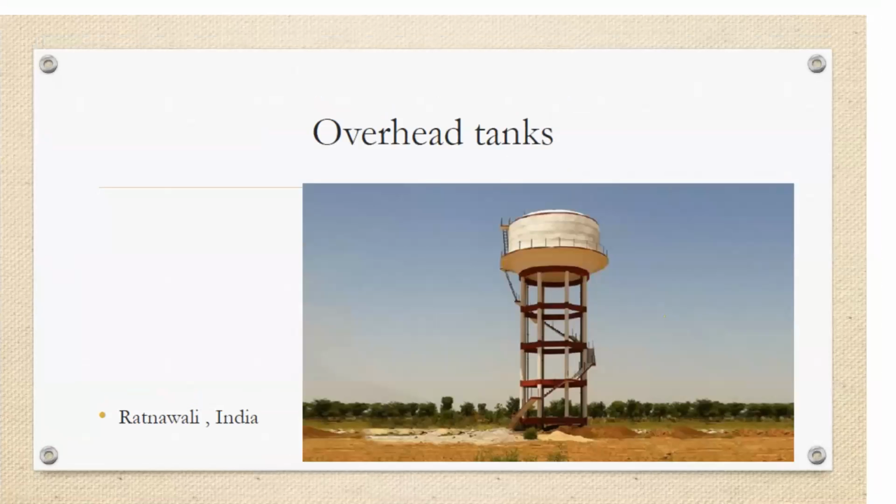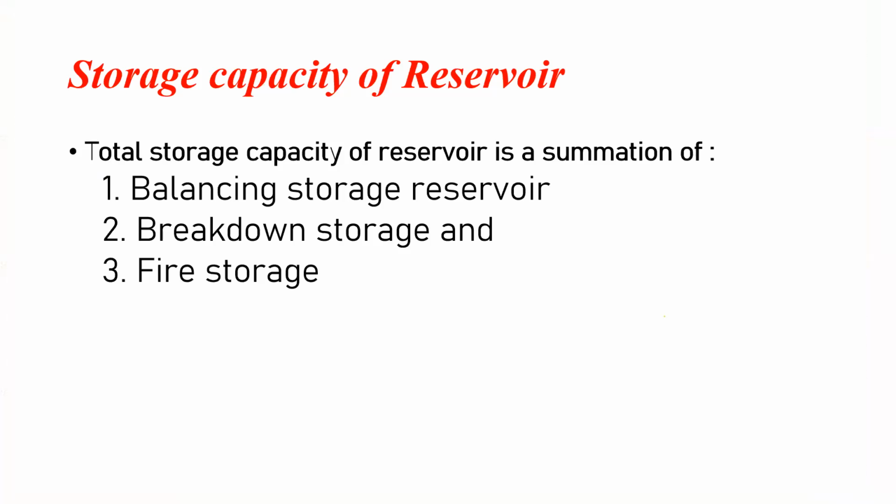Okay. Now, storage reservoir capacity. Now we need to decide what capacity of reservoir should be built, and you need to do a little calculation for this. And how can you decide the capacity of a storage reservoir? Storage capacity of reservoir: the total capacity of a reservoir is a summation of balanced storage, breakdown storage, and fire storage. Please note down this point. I will explain what is balanced storage, what is breakdown storage, and what is fire storage.